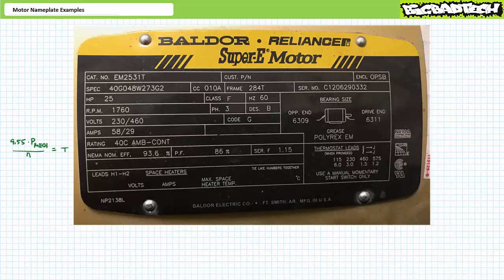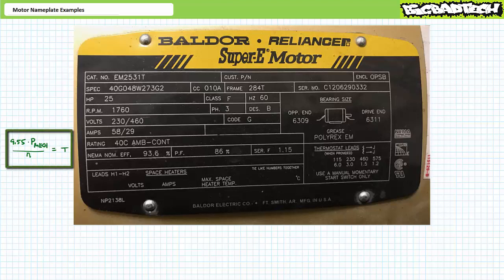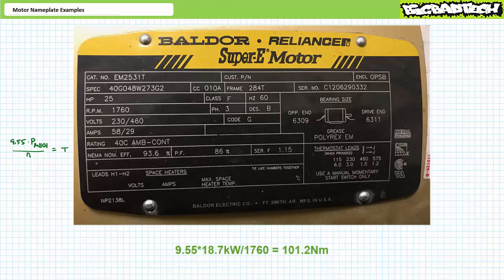While we've got this data in front of us, what is the rated torque? It's not specified on this particular nameplate; however, we can easily back-calculate it. An algebraic manipulation of the mechanical power formula solving for unknown torque demonstrates that torque equals mechanical power times 9.55 divided by rotational speed. Substituting our given values demonstrates this motor produces roughly 101.2 Newton meters of torque at the rated condition.